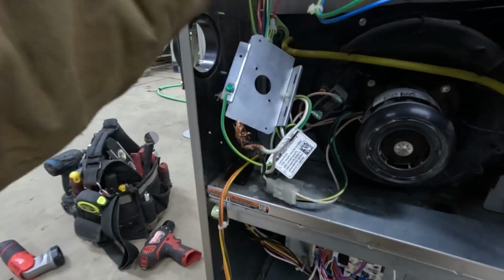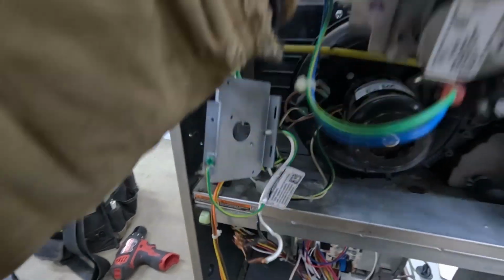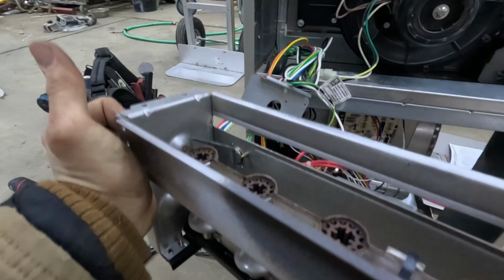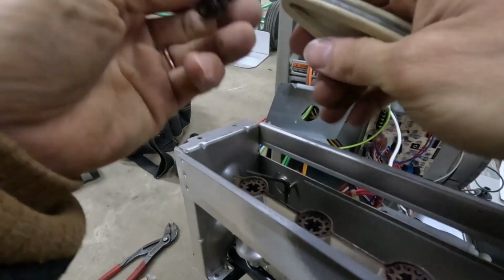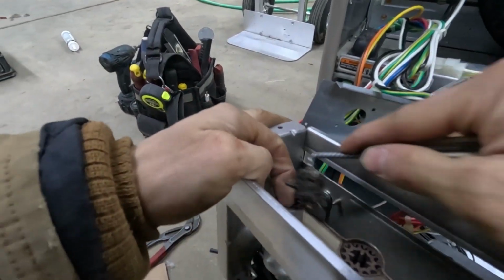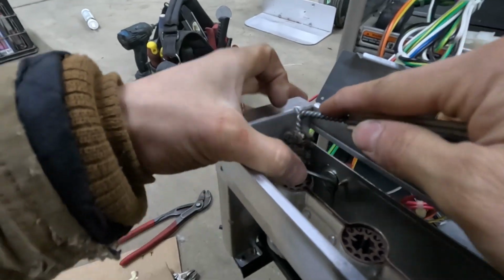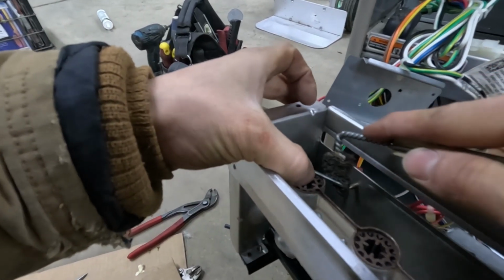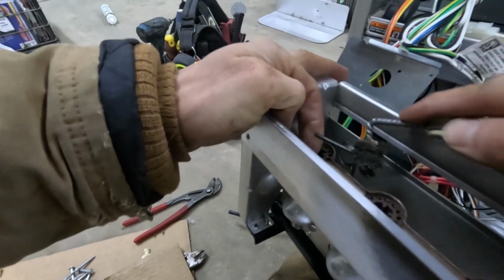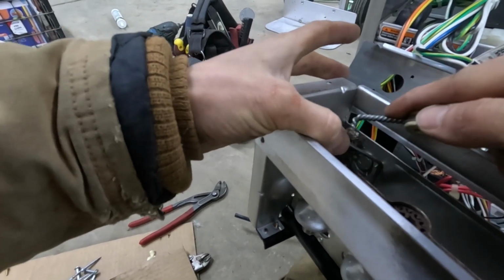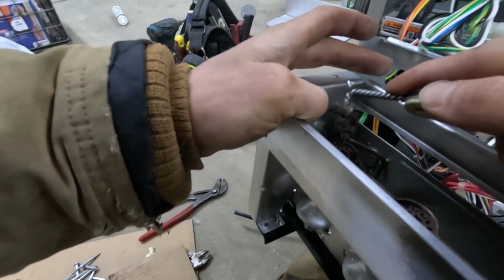Swing the burner assembly back up around. Oh yeah, I said we were going to maybe clean this flame sensor. For cleaning the flame sensor, you can either use a wire brush like this, which takes a little longer, or some emery paper, a type of sandpaper. Since we've got it opened up and it's easy to get to, we can just clean it quick.